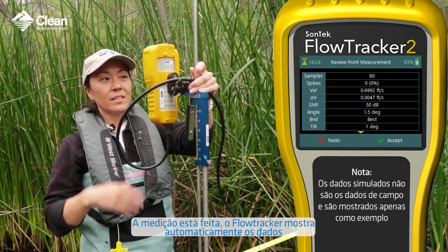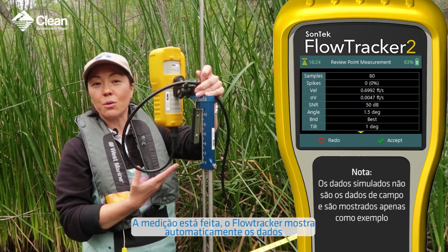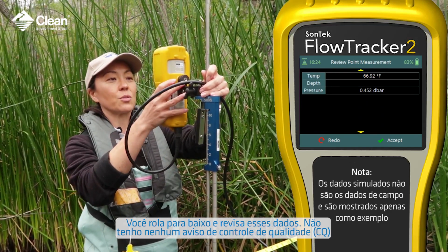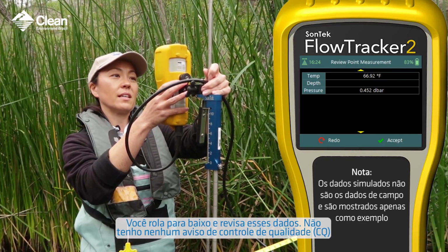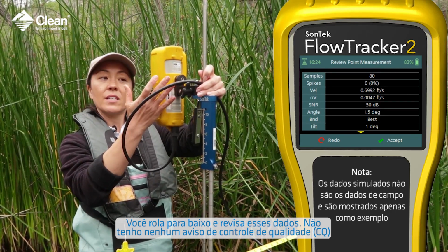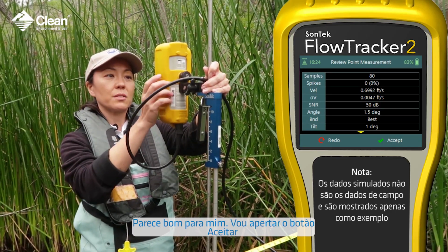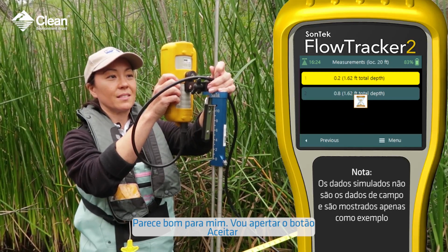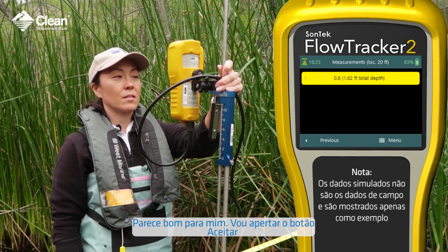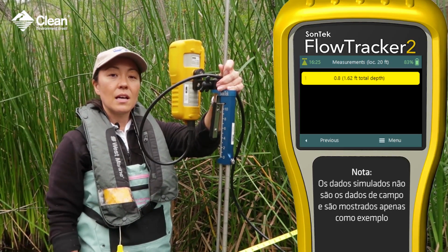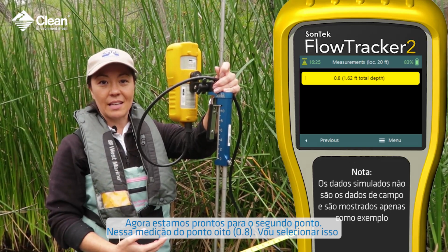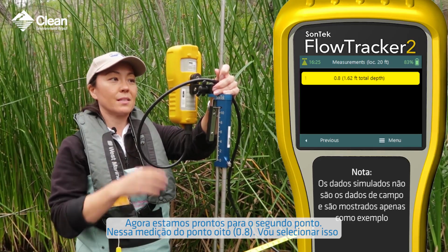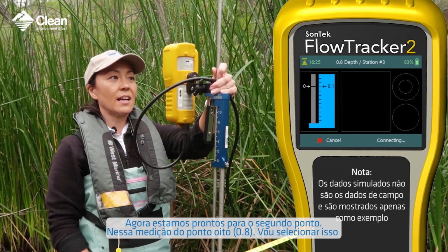The measurement is done. The FlowTracker automatically shows me the data. Let me scroll down and review that data. I don't have any QC warnings. Looks good to me. I'll hit the accept button. Now we're ready for the second point in that measurement, the 0.8 measurement. I'm going to select that.